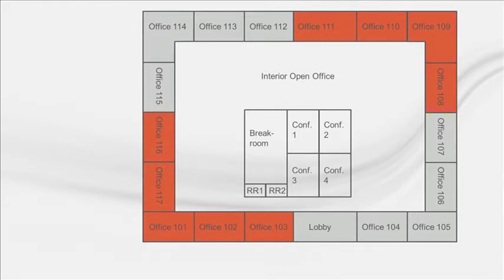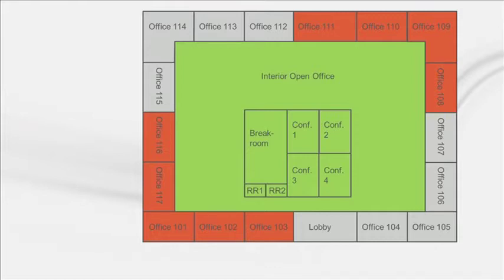The remaining interior zones might be best served by a heat pump system since they will likely need cooling year-round with only morning warm-up. Like the example from a few minutes ago, you might run into trouble with respect to ASHRAE Standard 15 requirements if refrigerant piping crisscrosses the building. If the zoning makes sense, we can now use the software's output reports to select equipment using the VRF manufacturer's selection software. We could also continue with an energy analysis.